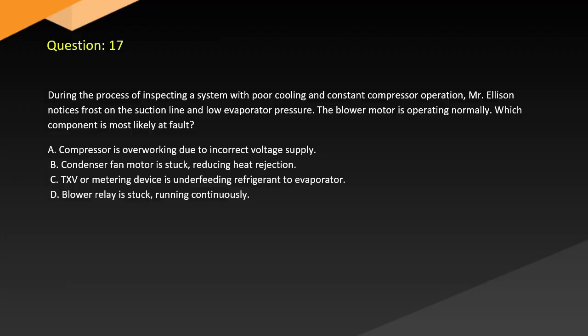Question 17. During the process of inspecting a system with poor cooling and constant compressor operation, the technician notices frost on the suction line and low evaporator pressure. The blower motor is operating normally. Which component is most likely at fault? A. Compressor is overworking due to incorrect voltage supply. B. Condenser fan motor is stuck, reducing heat rejection. C. TXV or metering device is underfeeding refrigerant to the evaporator. D. Blower relay is stuck, running continuously.